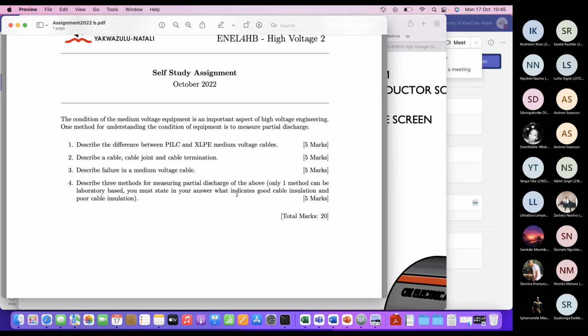So I got answers such as the leakage current is higher in poor cable insulation, or the tan delta is higher. The assignment was about partial discharge. So those things may be true, but what I really wanted was partial discharge. So it could have been the frequency, or sorry, the repetition rate of the partial discharge. It could have been the values of the partial discharge. You could have related that to whether it was good insulation or poor cable insulation.